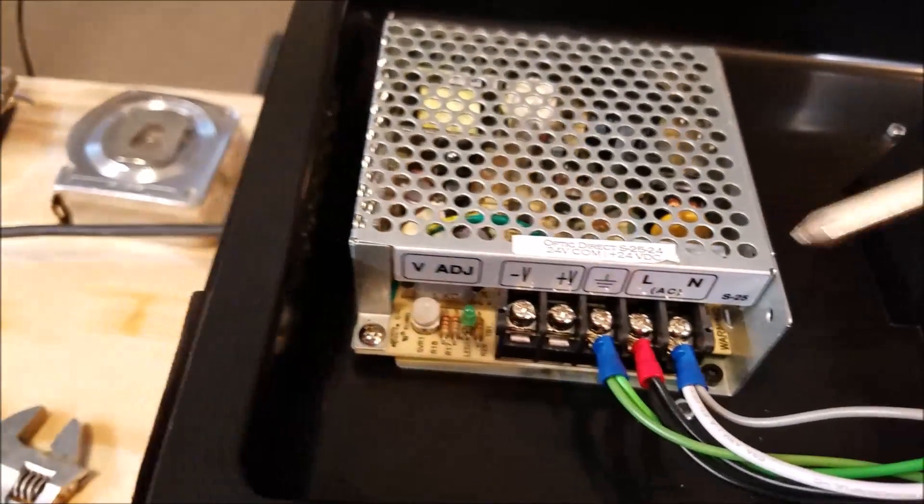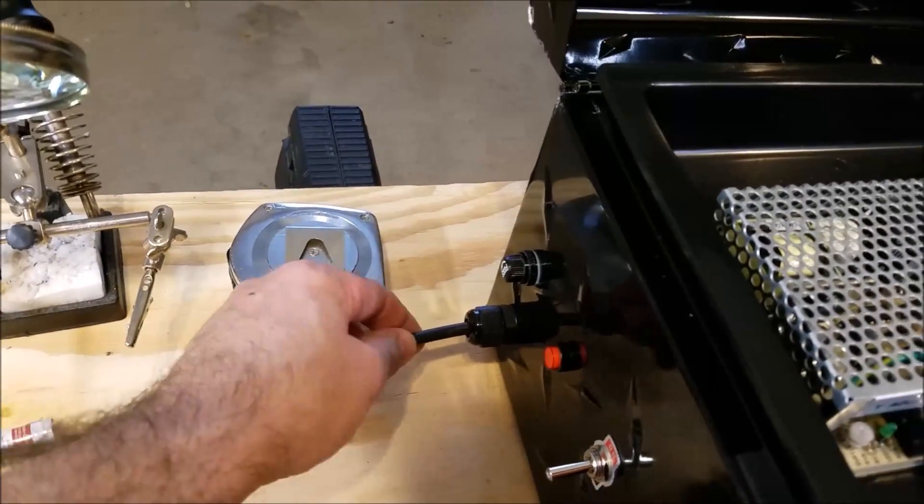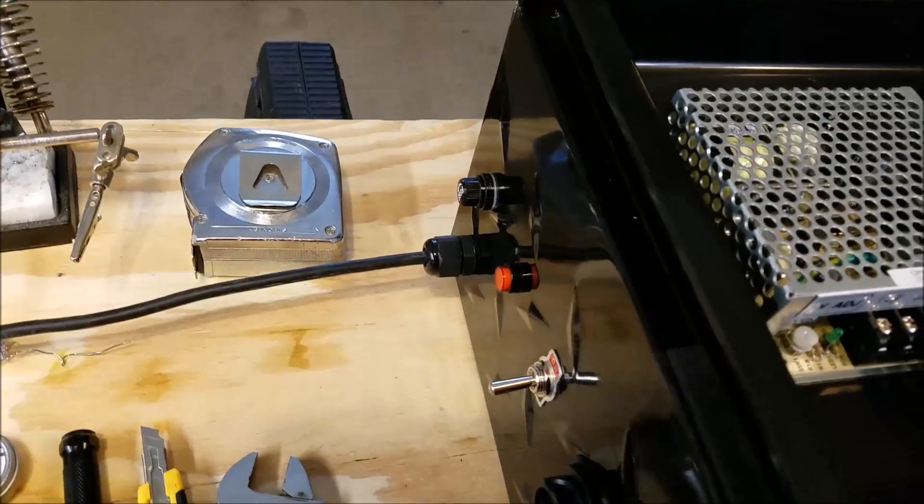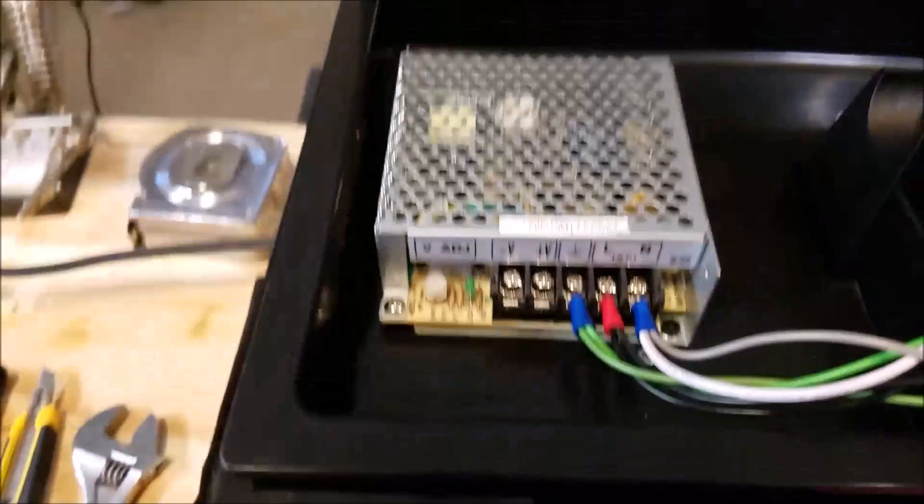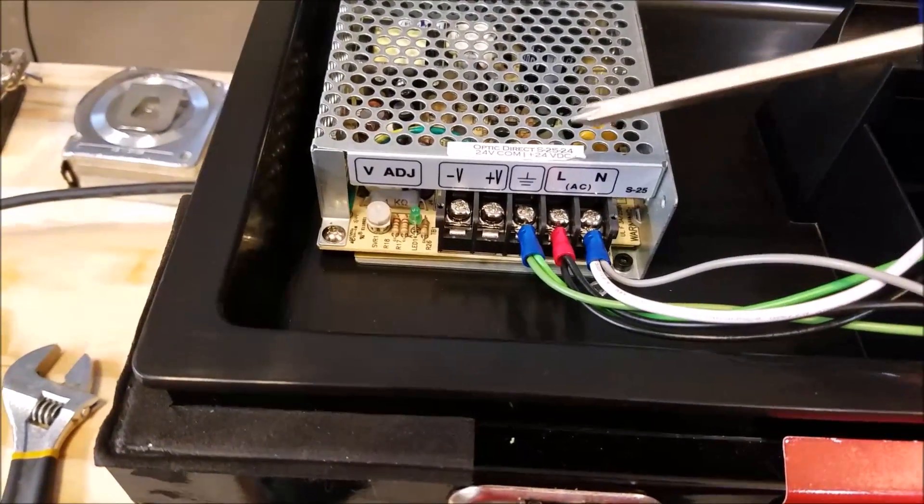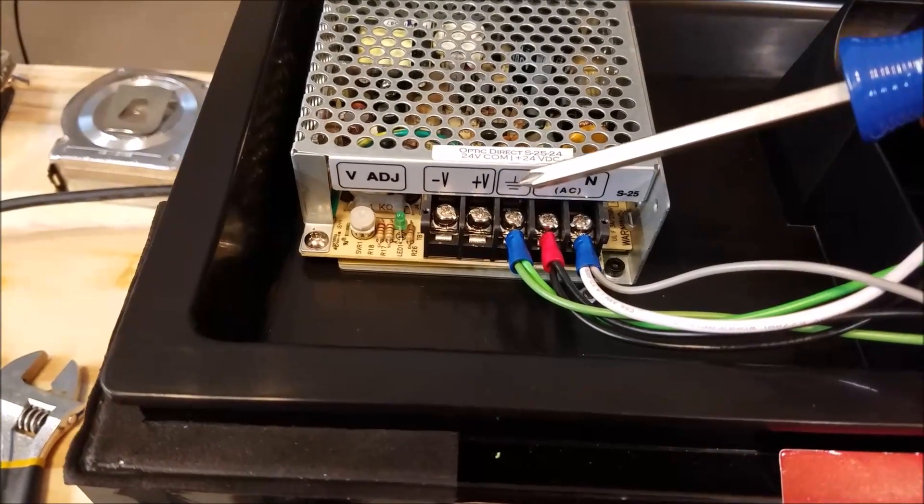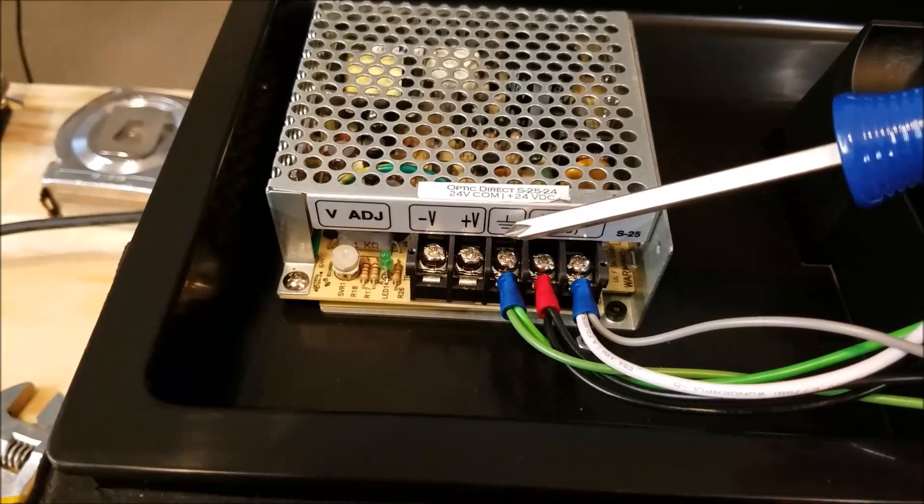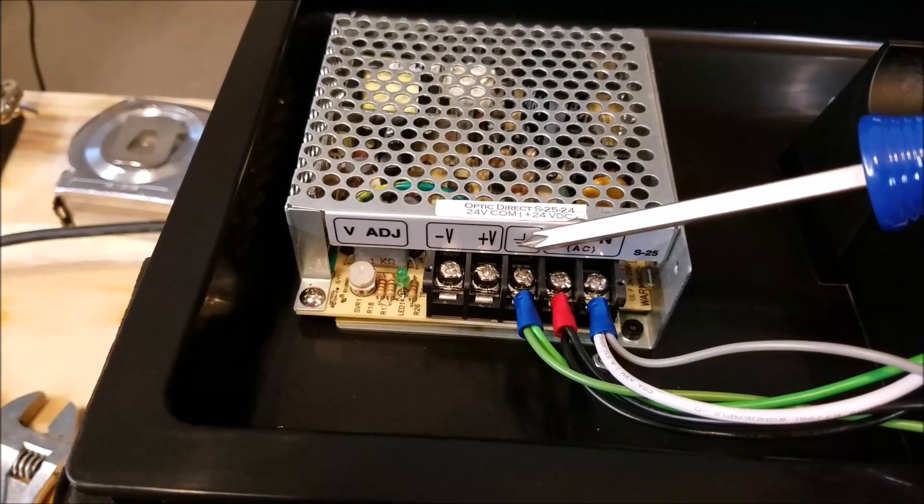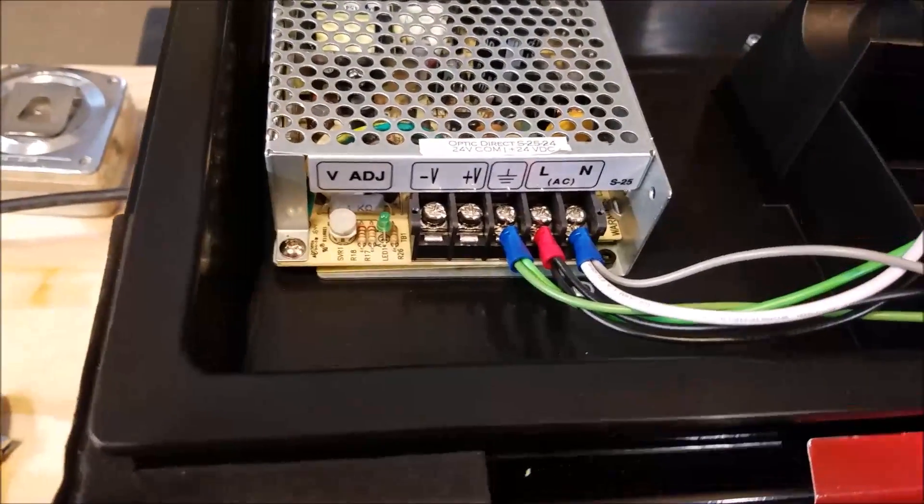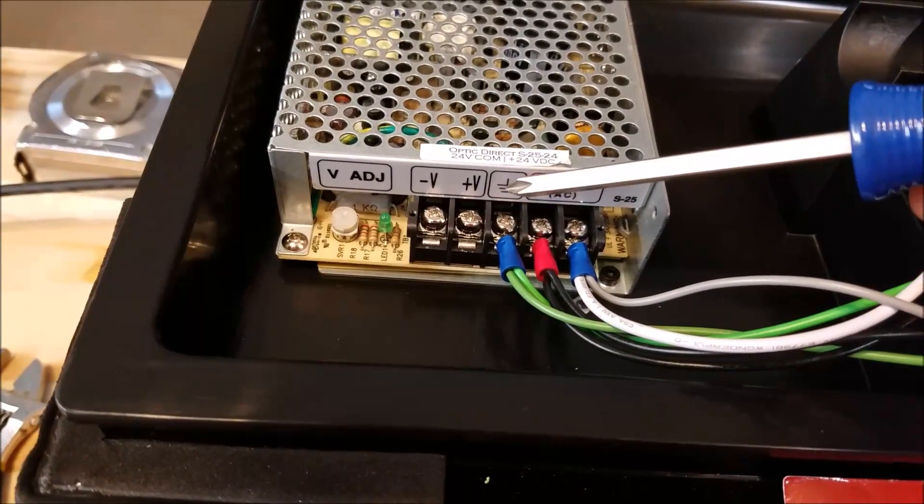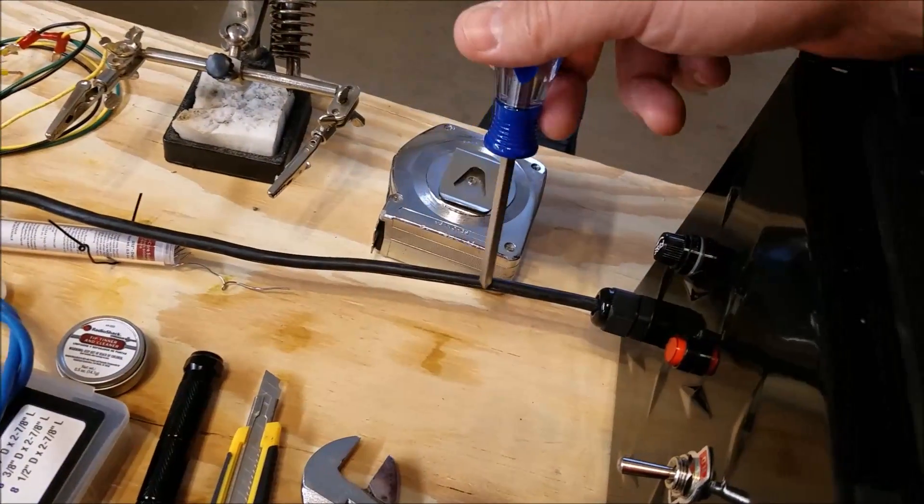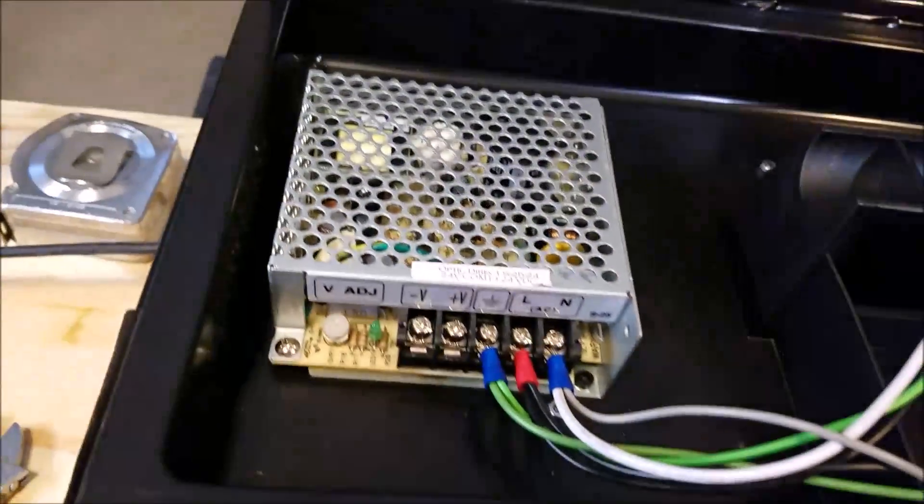So what you're basically doing here wiring up these power supplies is you're bringing 110 volts into the box, right? That's your source. And the first thing you want to do is, we'll just start with ground. Almost everything in here is going to have a ground terminal, so you can tie all these together. You want to tie all your ground terminals together somehow. Everything needs to be grounded. So that's pretty simple. There's a ground wire coming through this power supply, it comes into the box.